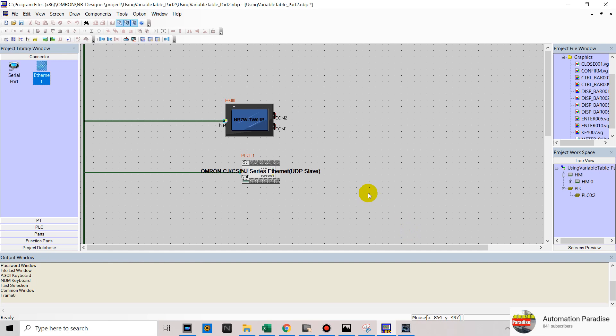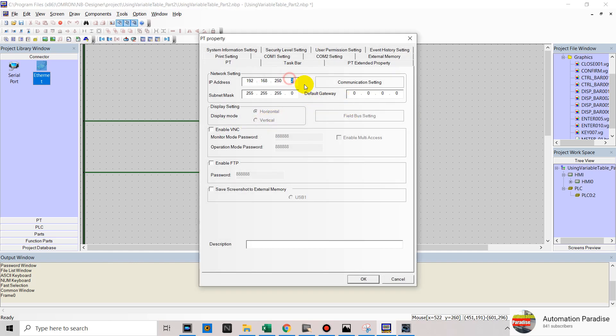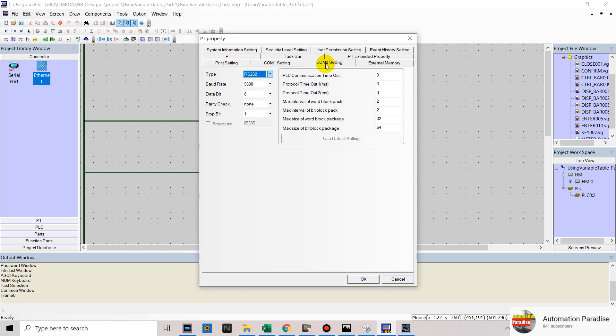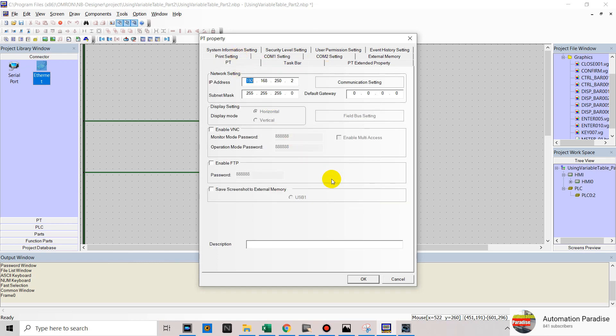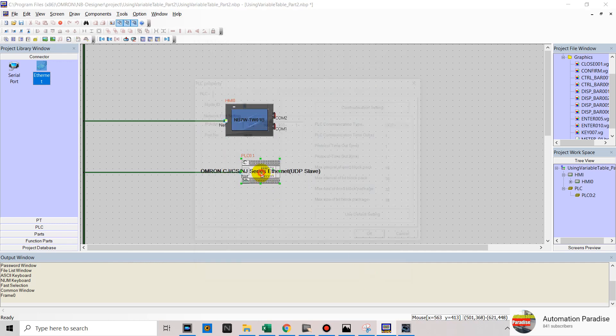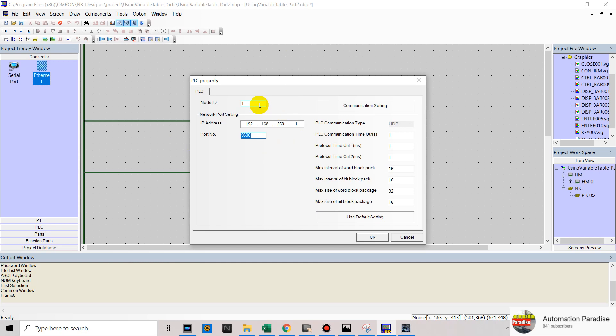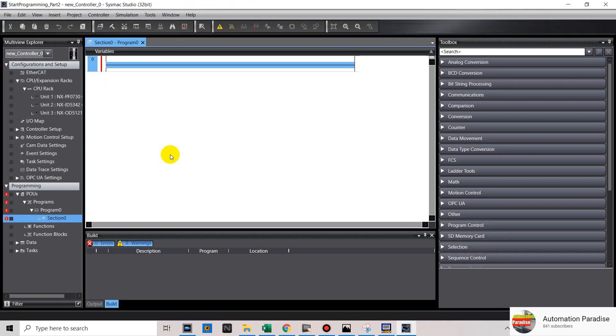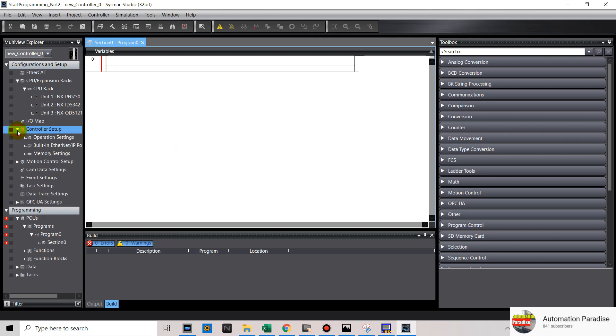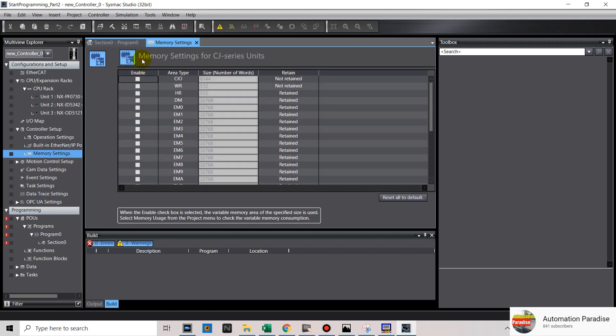Click OK. We will check our PT property and our PLC property. Now we need to enable the memory settings for CJ Series unit. In your SysMac Studio, double click on Controller Setup, then double click on Memory Settings. In the memory settings window, choose what device you need to use. As an example, we will enable CIO, WR, and DM area type.